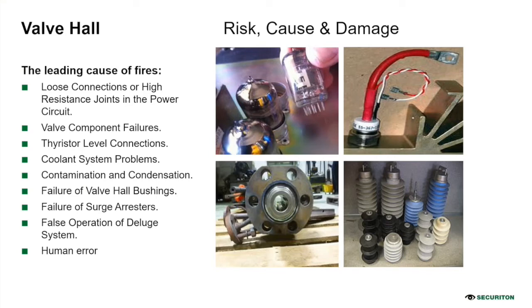Now, there are a lot of risks in designing the fire alarm system. A few of the leading causes of fire in HVDC application are loose connections or high resistance joints in the power circuit. I will explain one by one what this is. A power circuit is defined as a circuit which is used to carry electricity that operates a load. A high resistance connection, which we call HRC, is a hazard that results from a loose or poor connection. So if there is a poor connection, it can cause fire anytime.